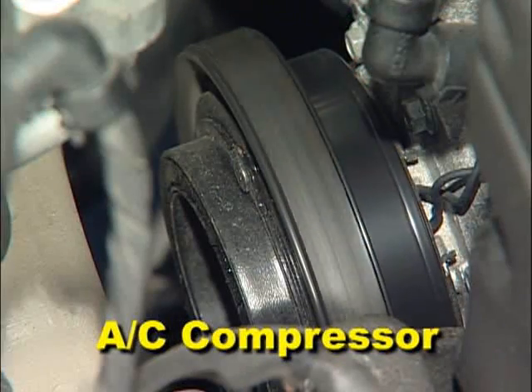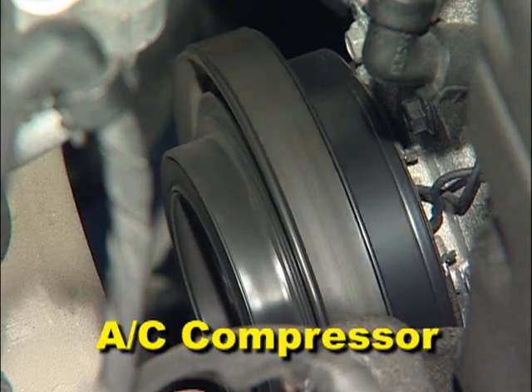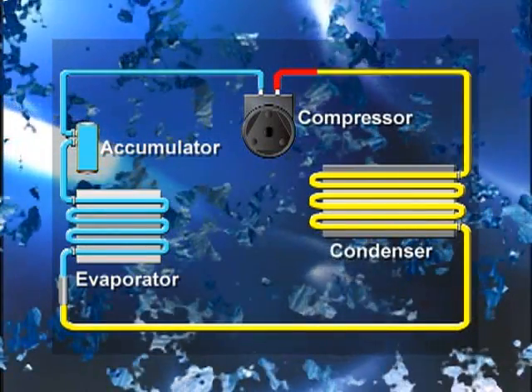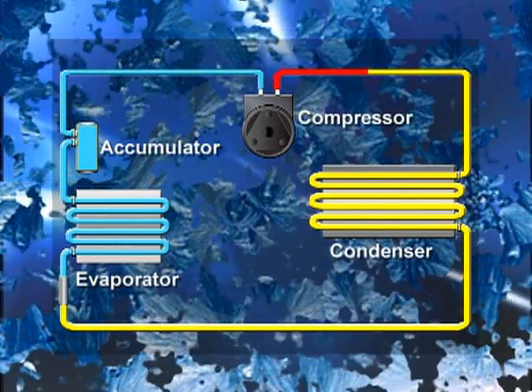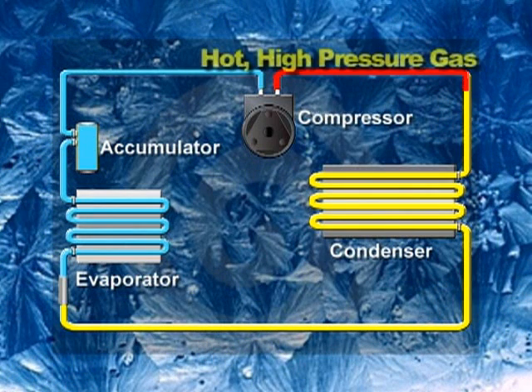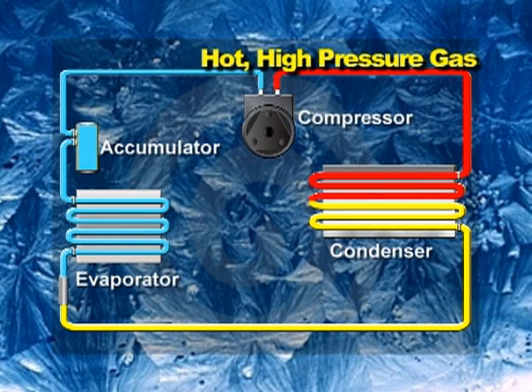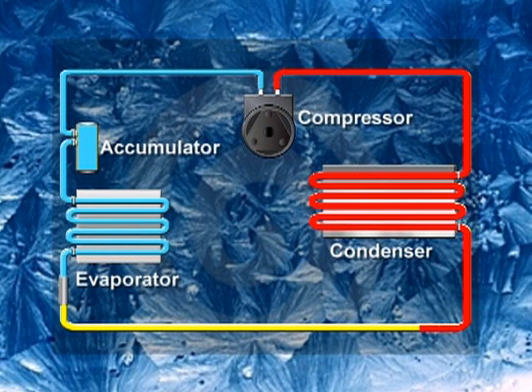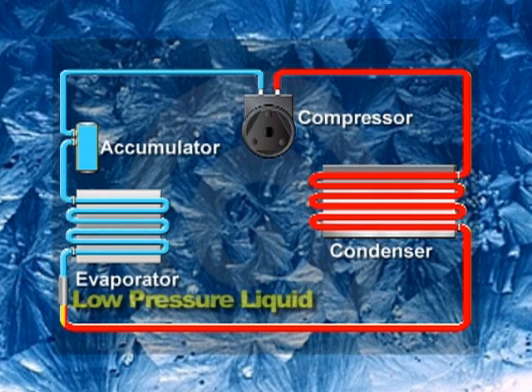The compressor is the only component with moving parts. It's a pump that compresses the refrigerant, turning the cold, low-pressure gas to a hot, high-pressure gas. As this hot refrigerant gas runs through the coils in the condenser, it gives off heat. The refrigerant then moves through a metering device, where it becomes a low-pressure liquid.